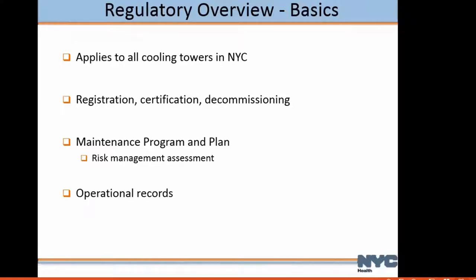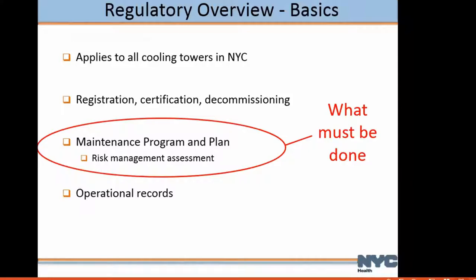The biggest requirement is the maintenance program and plan, which consists of a risk management assessment. All of those plans are based on identifying the risk and figuring out what to do. We require a maintenance program and plan in place for cooling tower systems — this is the building owner telling us what they're going to do to manage that engineered system.